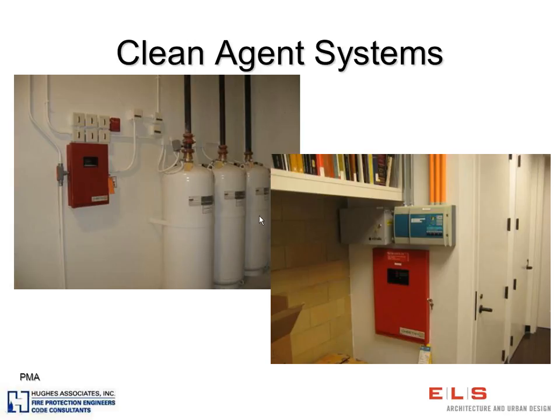So here are your canisters that are actually holding your gas, the fire alarm control panel, and then this element right here, this is actually your air sampling detection system. So it's the fan that's sucking in air, and these are the tubes that are going out into your space where your detection system is located, and that is protected by your clean agent system. So if you have a fire in the room, you have these tubes that are sucking in air, smoke is detected, it sends a signal to the panel, which sends a signal to the clean agent system and says you need to discharge, there's a fire in the room, and it trips the system and actuates.